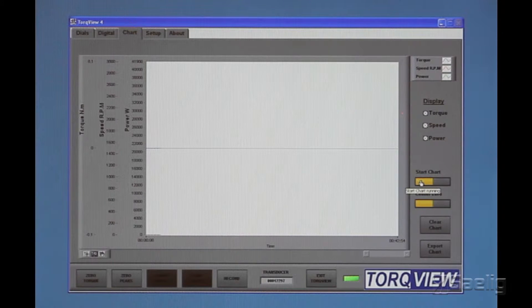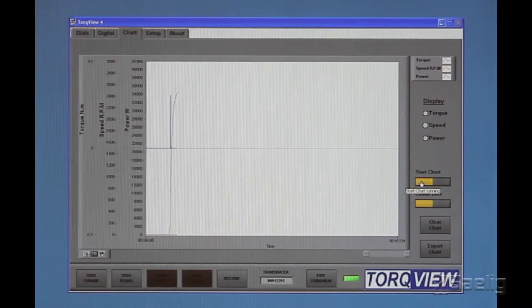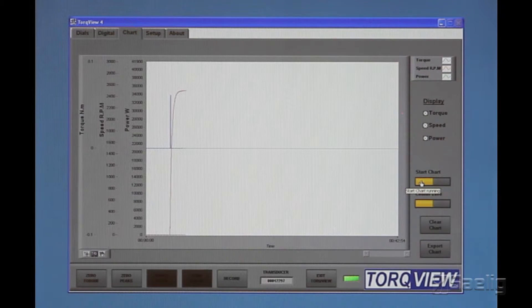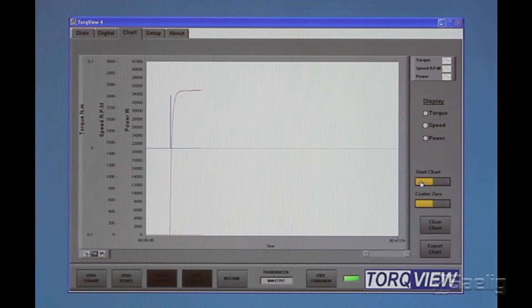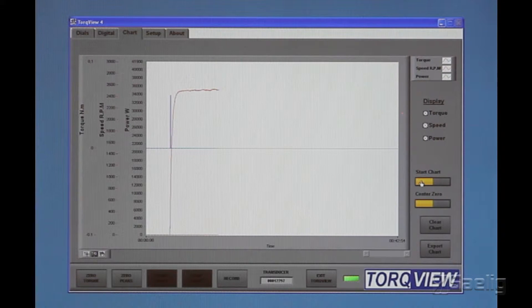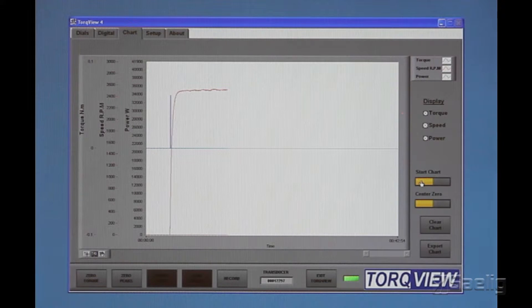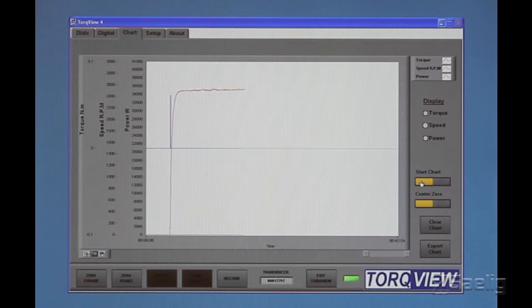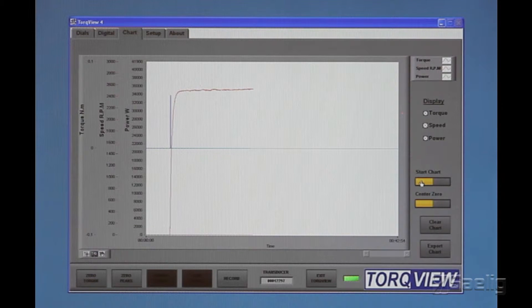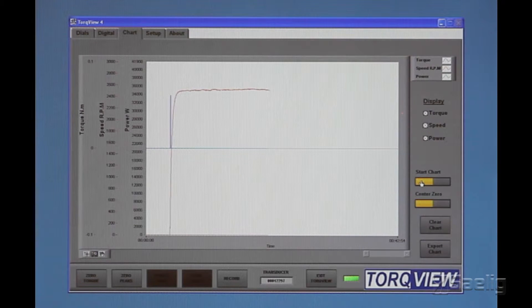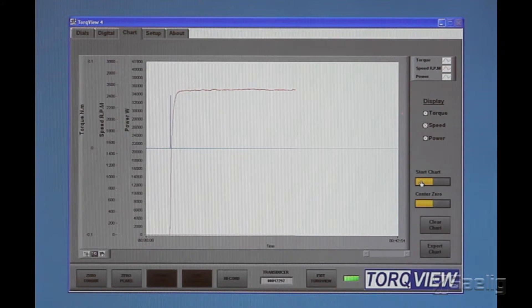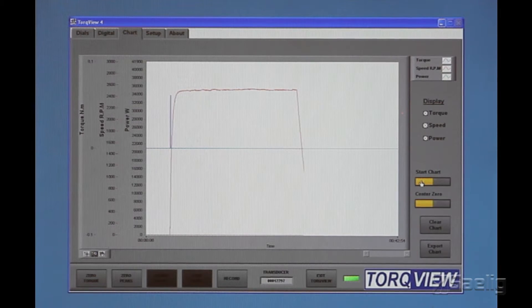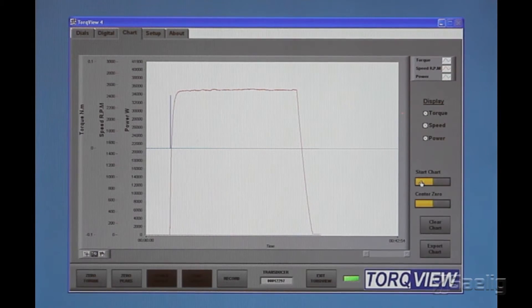Okay, so here we go. Bingo. So there's the speed starting, and it had to accelerate the handle. There's a circular handle on this transducer, and had to get that mass up to speed, and that's the little impulse that resulted from it.